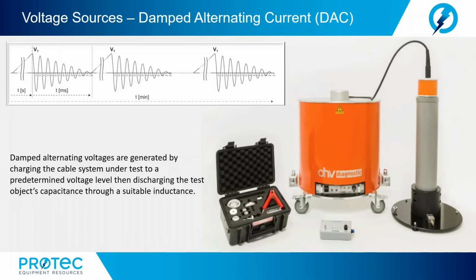Hz. Damped alternating voltages are generated by charging the cable system under test to a predetermined voltage level, then discharging the test object's capacitance through a suitable inductance. During the charging stage, the test object is subjected to a continuously increasing ramp voltage. During the discharging stage, the test object experiences a damped oscillating wave.